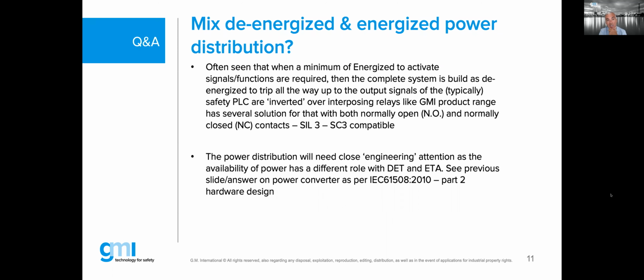But often what we see in the industry is that engineers will not use that type of line monitoring module. They will actually use normal modules, and they will move that intelligence into the interposing smart relay, such as the ones GMI is providing in the market. So no matter how you solve your final solution to energize to activate, you need to think about what is the most cost-effective way to do it, as long as you are not losing the functionality of such line monitoring, not by the module or by the relay. That's also why I said smart relays can feed that information back into the system.